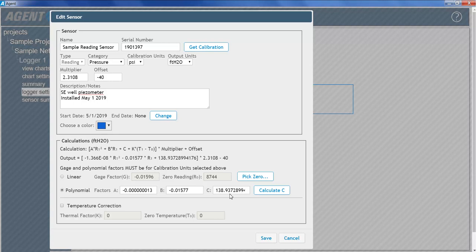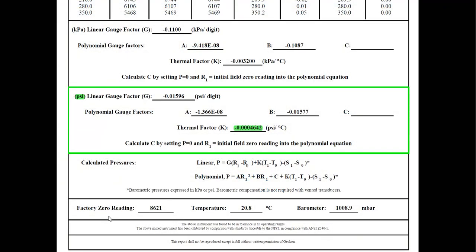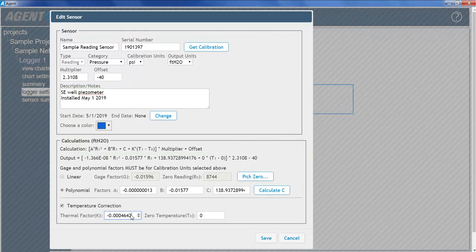For optimum accuracy, or if ambient temperature changes are large, a temperature correction can be applied. Enter the appropriate thermal factor from the calibration report based on the calibration units that have been selected in Agent. Enter the temperature in degrees Celsius that was recorded when the on-site zero reading was taken.